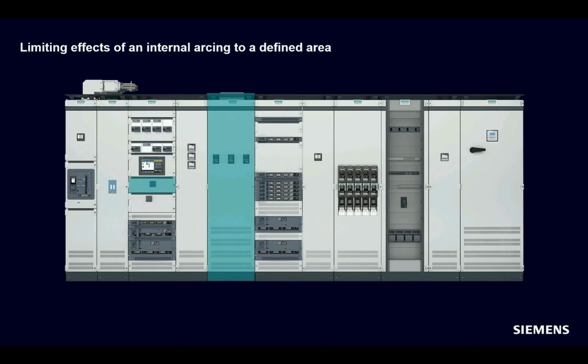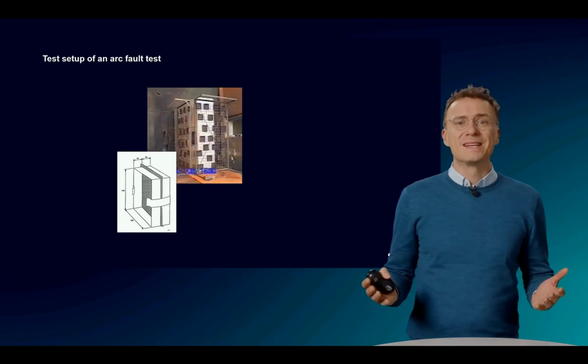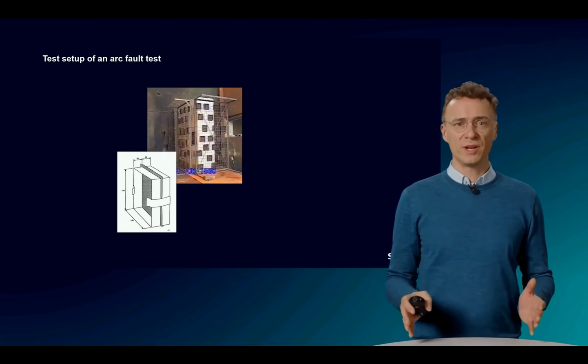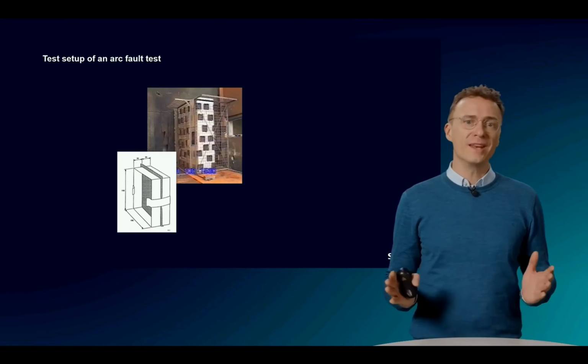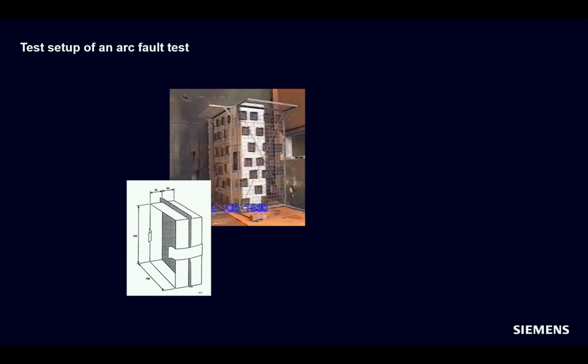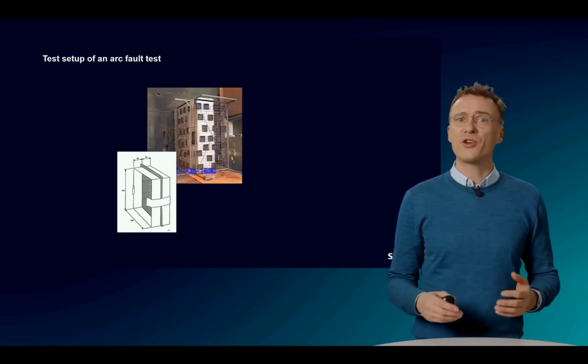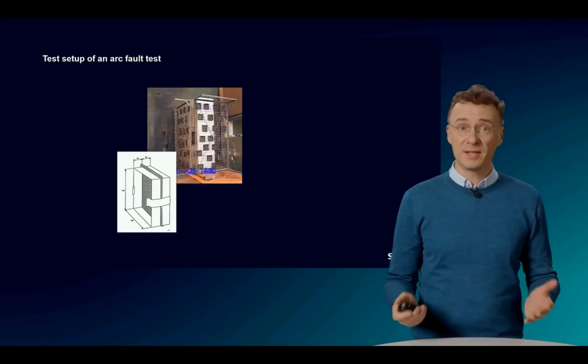After the tests, it's time to evaluate the test results. When is a test passed? Perhaps first a few words about the test arrangement. There's a grid standing in front of the test specimen. Attached to this grid are small rectangles of fabric, so-called indicators. These indicators are intended to simulate the clothing of a person standing at a short distance, approximately 30 centimeters, in front of the system. Two different fabric qualities can be used. A lightweight cotton fabric designed to replicate unrestricted access, like in leisure wear, or a heavy fabric of around 150 grams per square meter that represents the work clothes of staff with limited access.